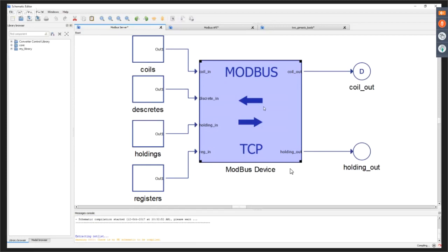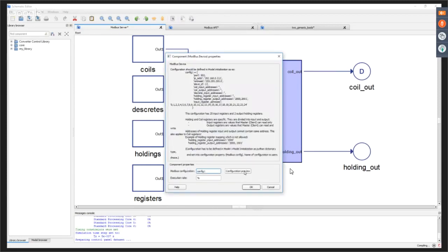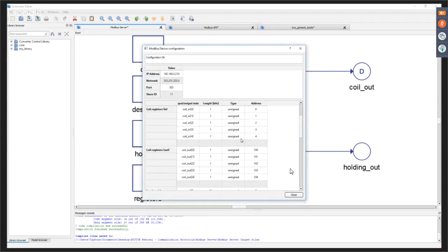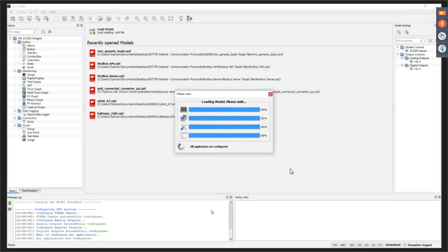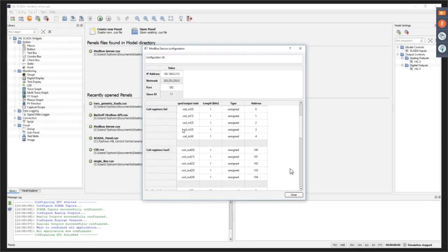While the configuration is compiling, we can see the configuration preview, as I mentioned, in the template form with communication part and register map part. Right. I'll just go quickly back, explain it here. And you can see the input for Modbus device, which coil is for which Modbus input, the length in bits, type of register, and address. If we go down to the input registers, you can see type of unsigned integer, float, and the 32-bit, 64-bit, 16-bit registers, and all the addresses.